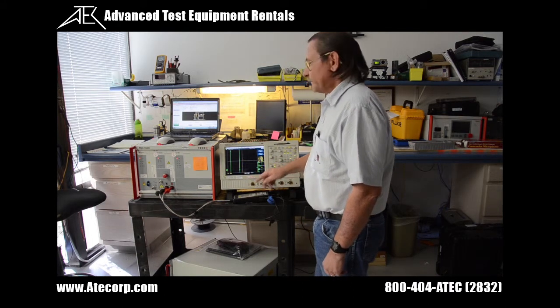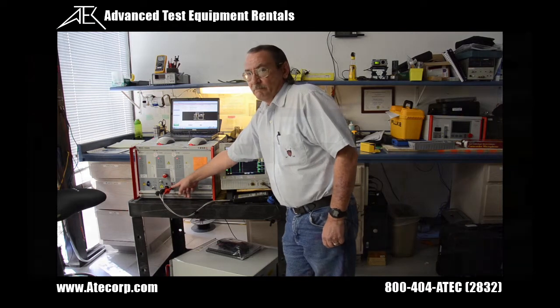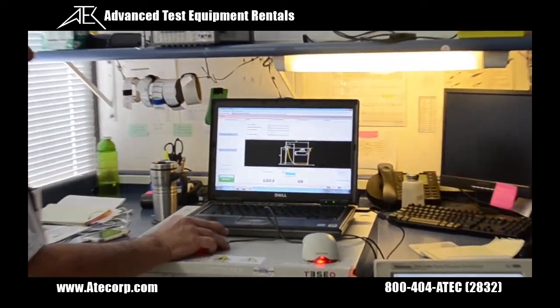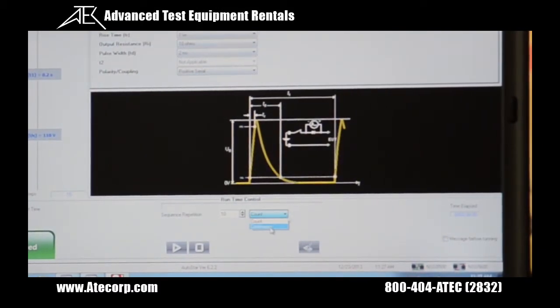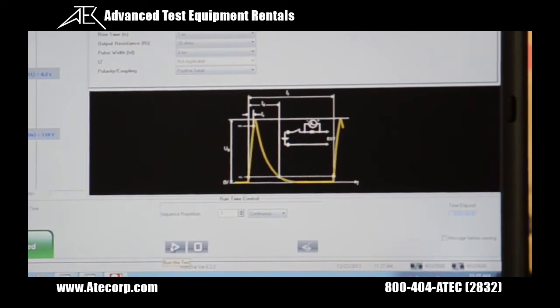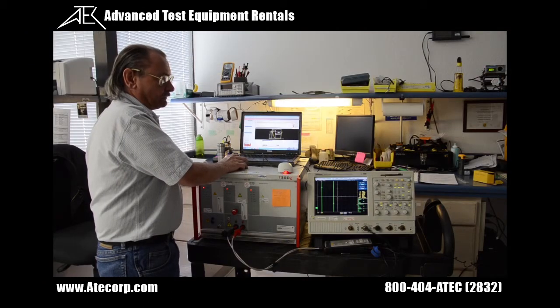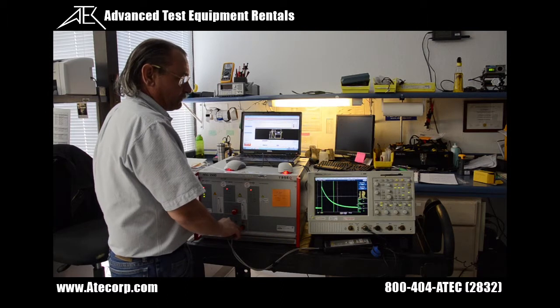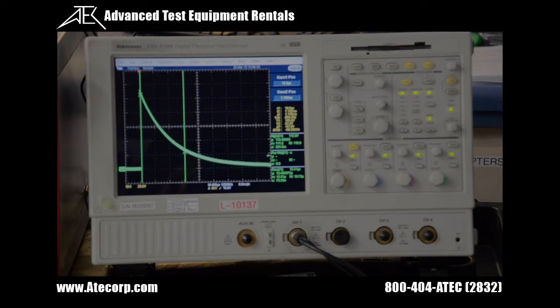I'm measuring it using a differential probe going through the supplied adapters to the 5530. On your pulse, you can select by the drop-down whatever count you want — for instance, 10, or if you want it to run continuous. I'm going to run it continuous; it will run until I stop it. I'm now running a continuous pulse that's being monitored through my differential probe to the O-scope. The scope now shows a representation of the waveform being produced. The measurements of the waveform can be shown on the diagram of the pulse, and it'll also show you where they are to be measured.